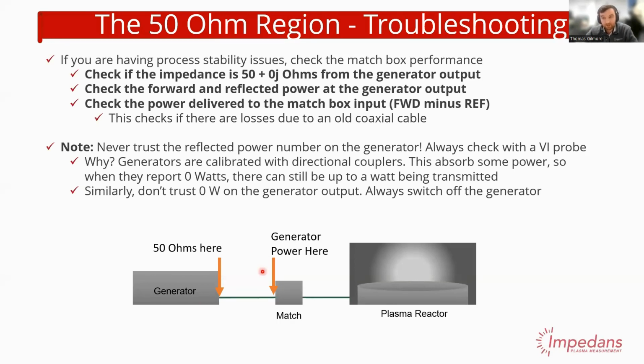The cable can also be faulty. Over time, cables go through heat cycles, which means they degrade—they get more resistive, their capacitance changes. They do have to be replaced occasionally. So you want to measure after the cable. By checking here, you're also checking what losses there are due to the coaxial cable.